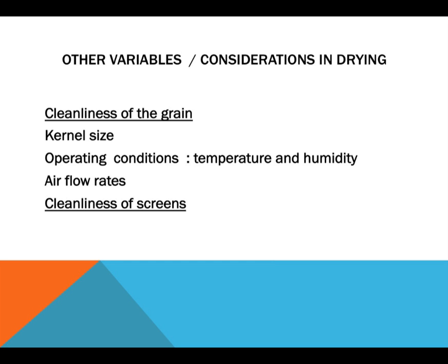We found many, many years ago when I was an active employee that the outside of the dryer, particularly on the tower dryer, and I'm not picking on towers, you'd see them get built up with this large, just god-awful red bee's wing, dirt, and dust that's hung on the outside. And we found that if we didn't get that cleaned off, the actual performance of the dryer dropped because we were tracking performance, okay? You could tell that you had to slow the feed rate down for the same moisture to try to get it through there.